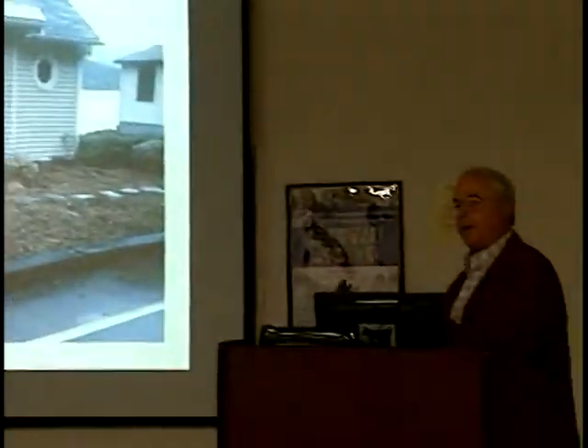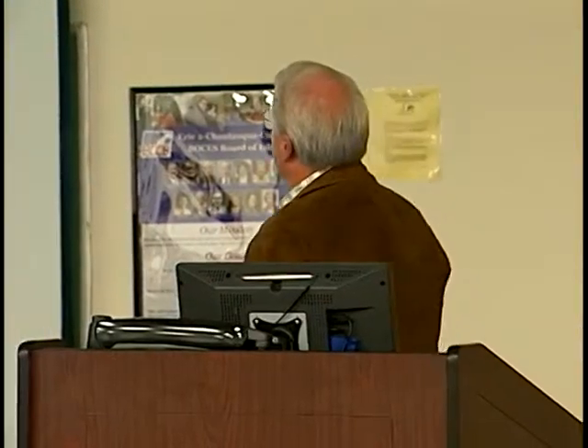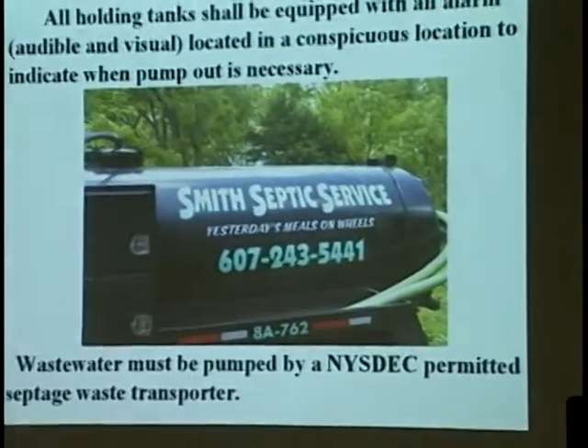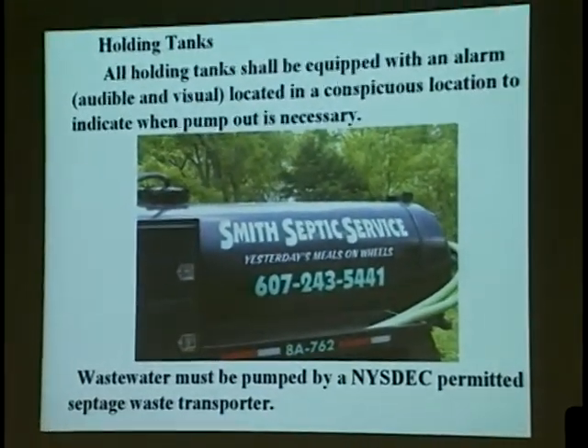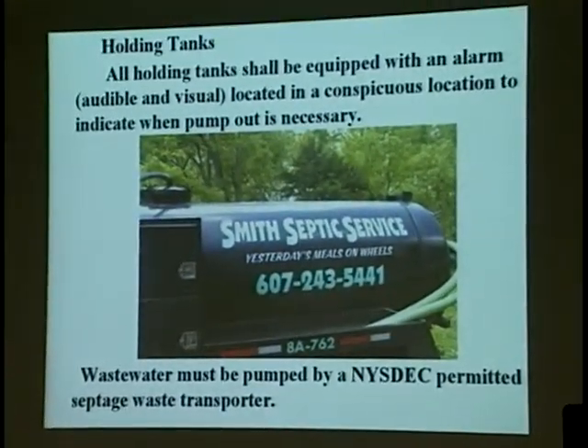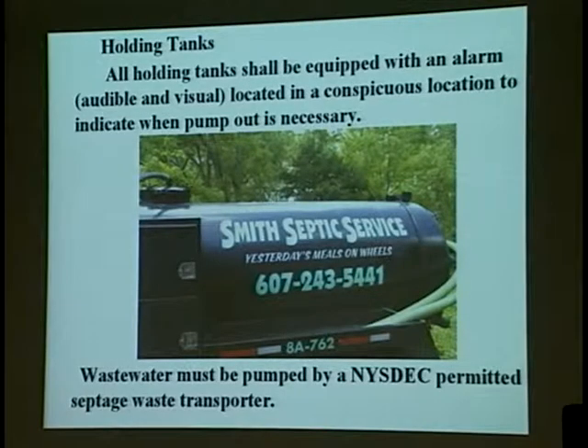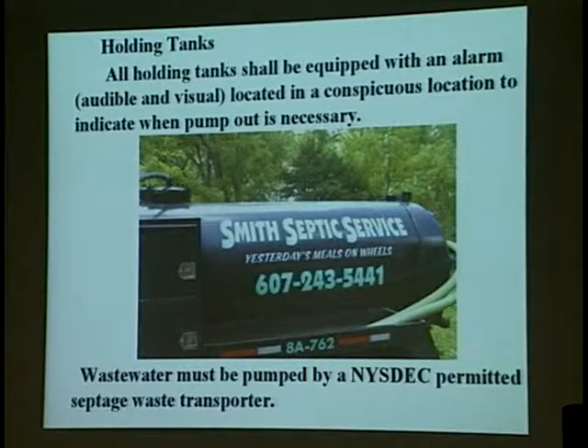This works as far as keeping the nutrients, bacteria, and other problems out of the lake, which is a drinking water source. We do require these holding tanks shall be equipped with an alarm — audible and visual — located in a conspicuous location to indicate when pump-out is necessary. Also, the wastewater must be pumped by a New York State DEC permitted septic hauler.